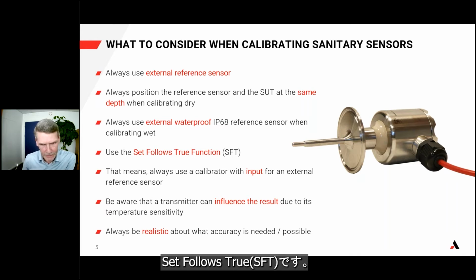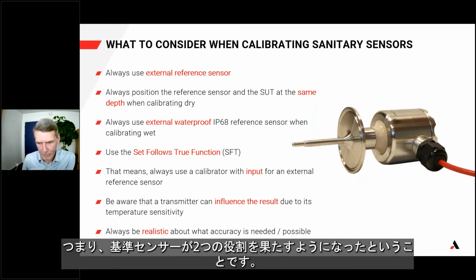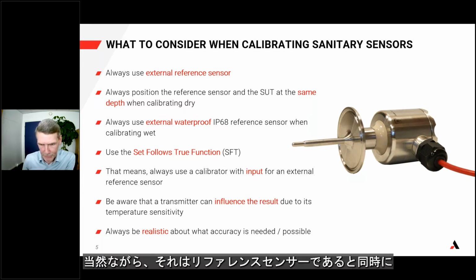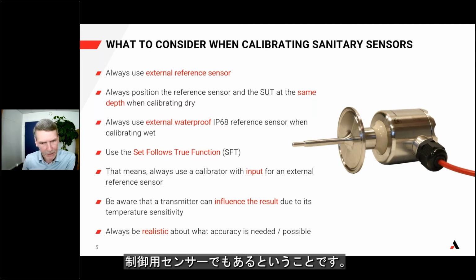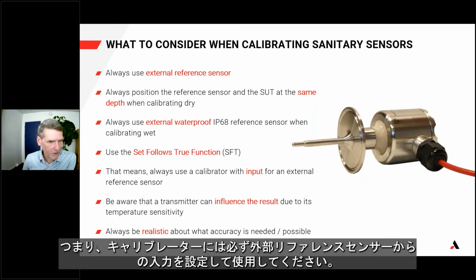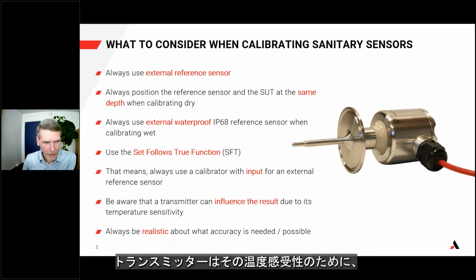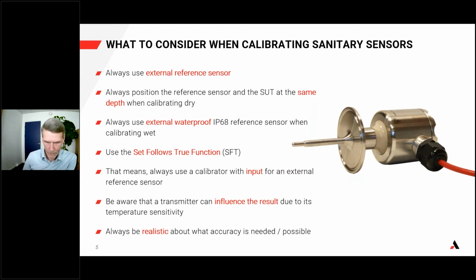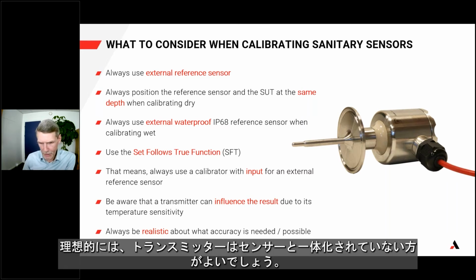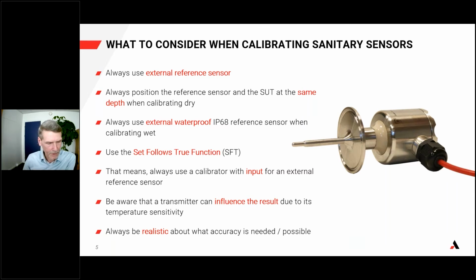Set follows true, SFT, means that the reference sensor now serves two purposes. Naturally, it is a reference and at the same time the controlling sensor. That means always use a calibrator with input for an external reference sensor. Be aware that a transmitter can actually influence the result due to its temperature sensitivity. Ideally, the transmitter should not be integrated with the sensor.